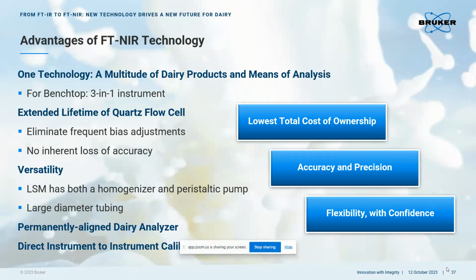With our portfolio of the different FT-NIR analyzers, we see the lowest total cost of ownership between the savings on maintenance costs, direct calibration transfer, and our all-in-one MPA2D that can measure both solids and liquids, you're eliminating the need for multiple instruments. And lastly, for our Matrix F2, this allows us to connect to different types of probes with different fiber lengths. And again, by utilizing only one spectrometer, you have markedly lower cost analysis, or cost per analysis point. And we get the same benefits of incredible accuracy and precision as we typically see with FT. We also get a myriad of applications that can be measured and processes that can be optimized. And most importantly of all, it's with confidence.